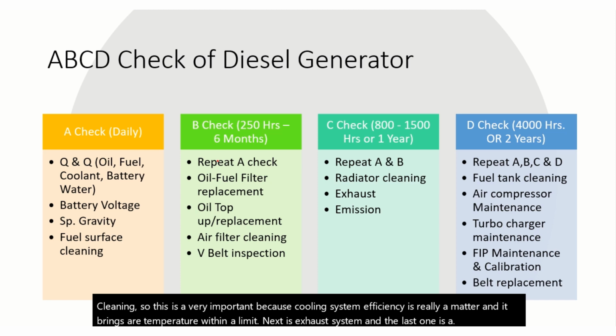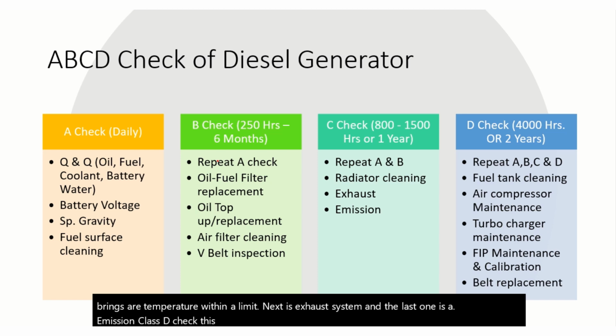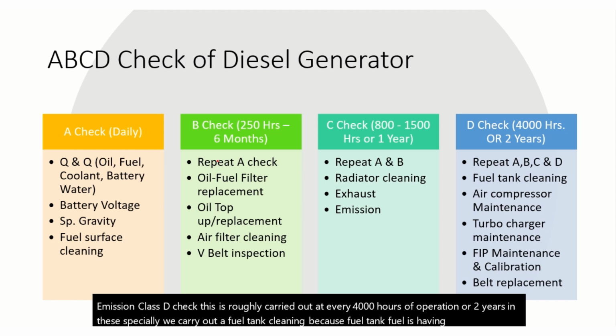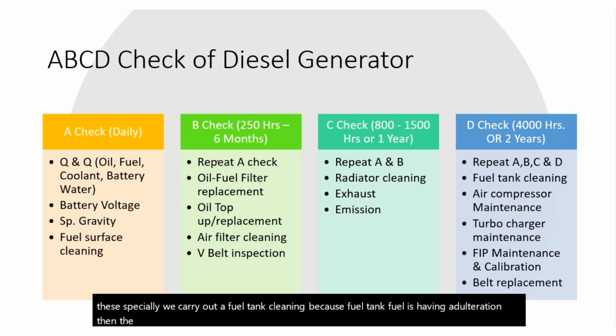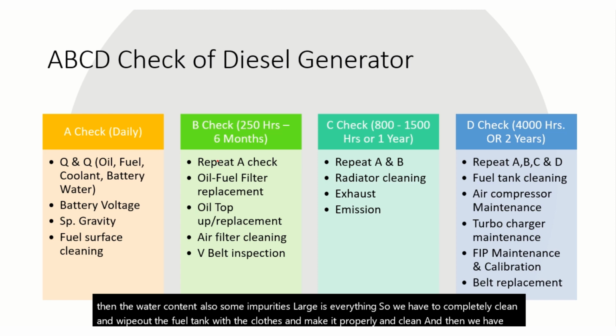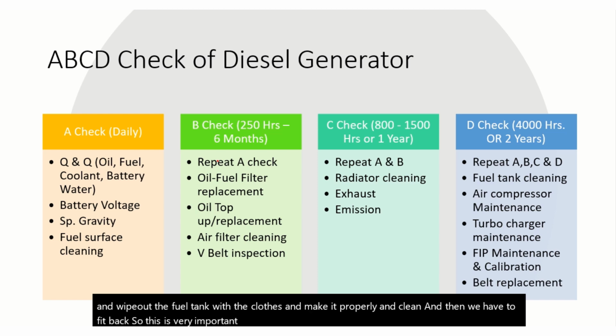Class D check is roughly carried out at every 4000 hours of operation or 2 years. In this especially we carry out fuel tank cleaning, because fuel has adulteration, water content, and also some impurities and sludge. So we have to completely clean and wipe out the fuel tank with cloths, make it properly clean, and then fit it back. So this is very important cleaning every 2 years. Normally industry carries out this kind of maintenance.